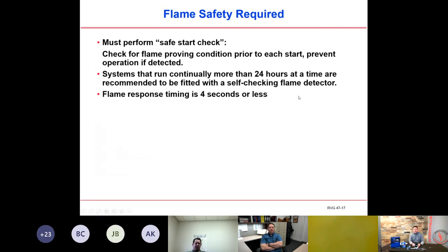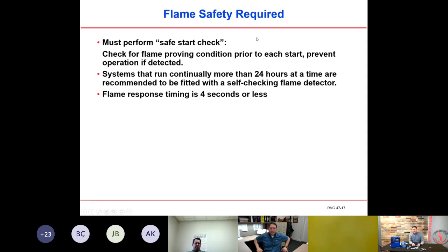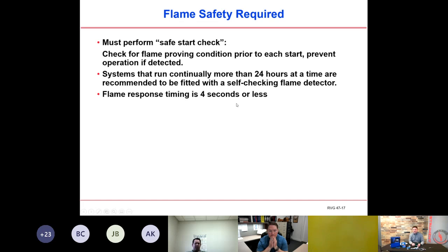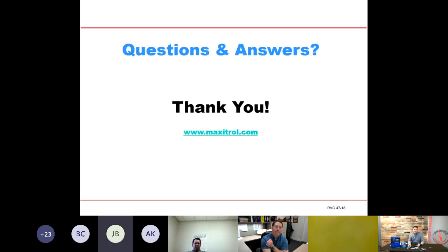To wrap up, here are some general flame safety rules of thumb. The flame safeguard must perform a safe start check — confirming no flame proving condition at the beginning of every startup. Systems running more than 24 hours must use a self-checking flame detector. The flame response timing on your amplifier must be four seconds or less — in the Honeywell world you have a choice between a three-second amplifier and a 0.8-second amplifier.